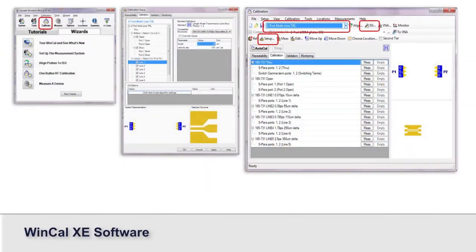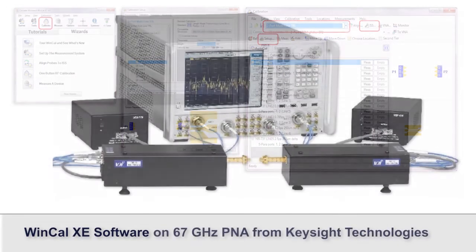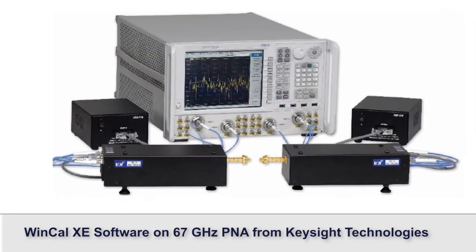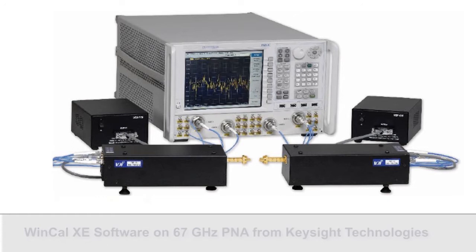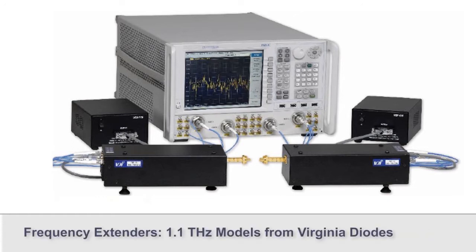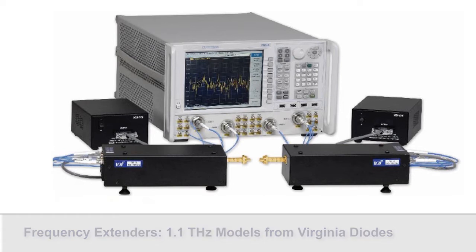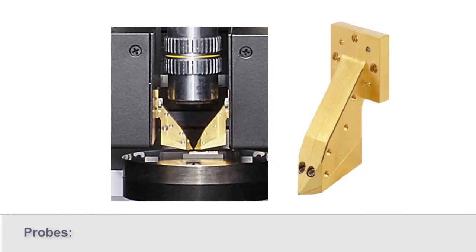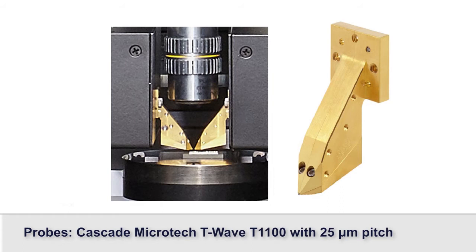We are running WinCal XE software directly on a 67 gigahertz PNA from Keysight Technologies. The frequency extenders are 1.1 terahertz models from Virginia diodes. The probes are Cascade T-Wave T1100 probes which have a 25 micron pitch.